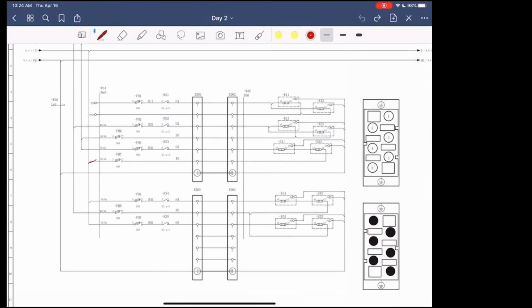So for example, this is line 3, and this only has a fuse on it. And if it goes here, and if it goes through the grounding, because it's shorted out, it'll complete the circuit. So again, that's another thing you have to be cautious of if you have a runaway heater. It could be either the solid state relay being stuck, or it could be a short circuit on your heater band.